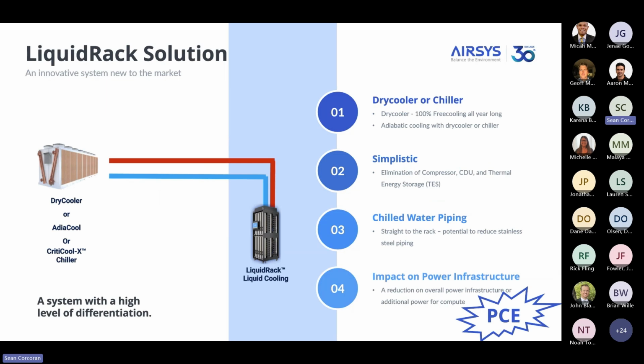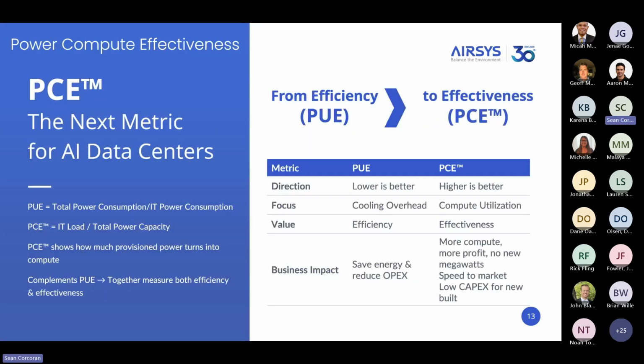The liquid rack solution. This is where we take a look at eliminating the mechanical side of things, because in the liquid rack, we do not have a CDU built in. It has no compressors, it has pumps, but depending on the temperature, you can either go with a dry cooler or with the chiller, depending if the chilled water temperature is higher or lower, one or the other, which helps then to talk about power compute effectiveness, right?